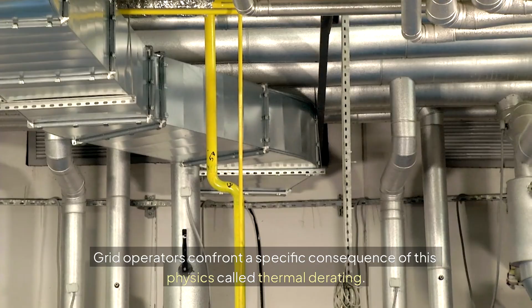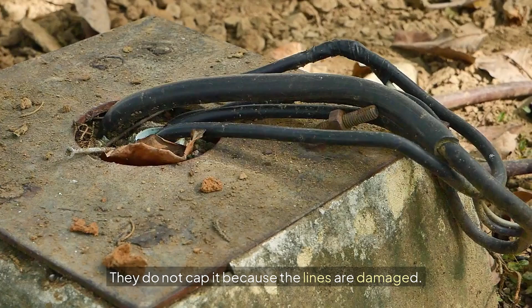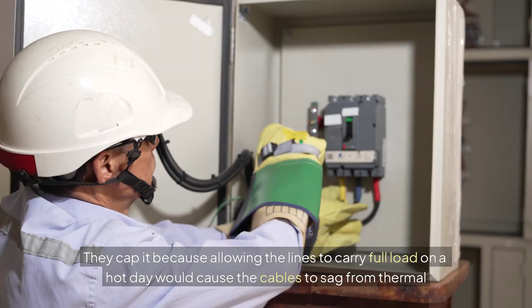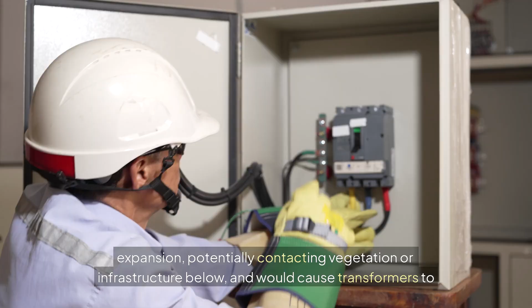Grid operators confront a specific consequence of this physics called thermal derating. On the hottest days of summer, when air conditioning demand peaks and electricity consumption surges to its annual maximum, grid operators are forced to artificially cap the amount of power flowing through their transmission lines. They do not cap it because the lines are damaged; they cap it because allowing the lines to carry full load on a hot day would cause the cables to sag from thermal expansion, potentially contacting vegetation or infrastructure below, and would cause transformers to overheat and fail.